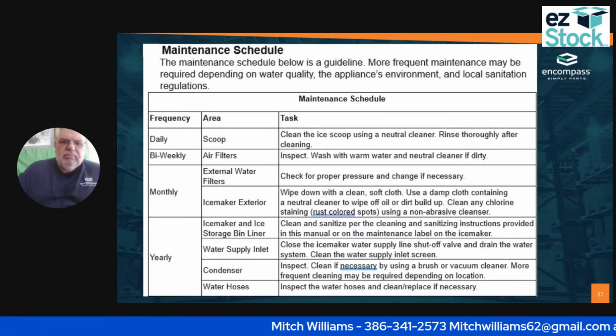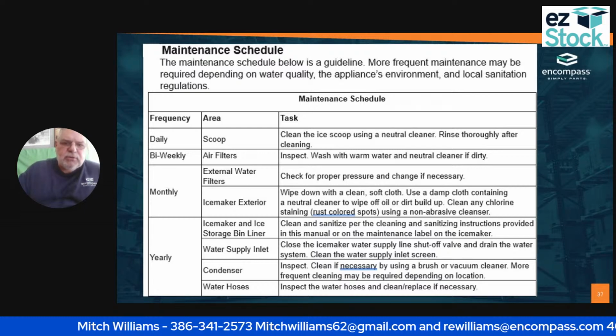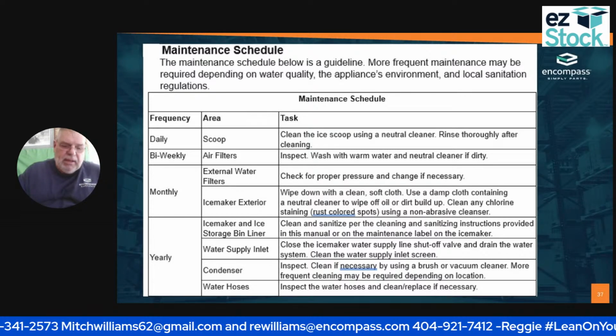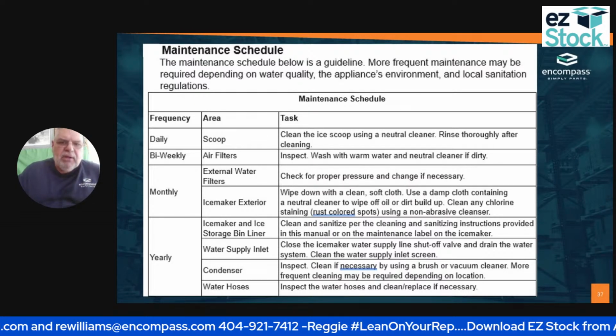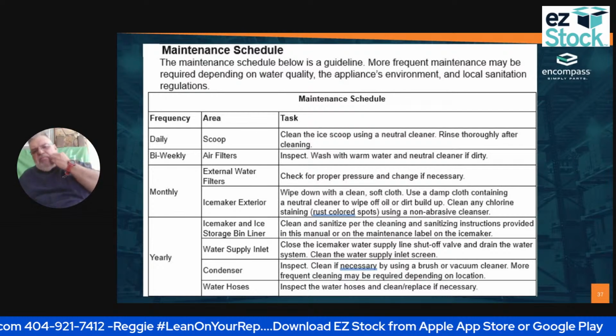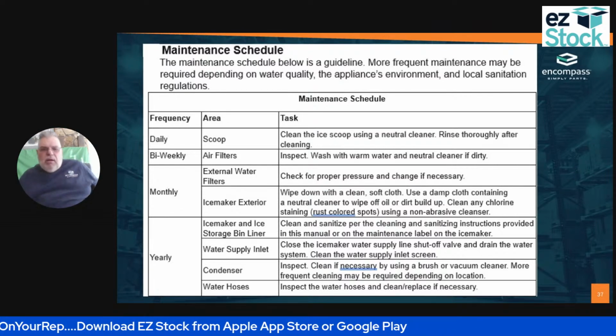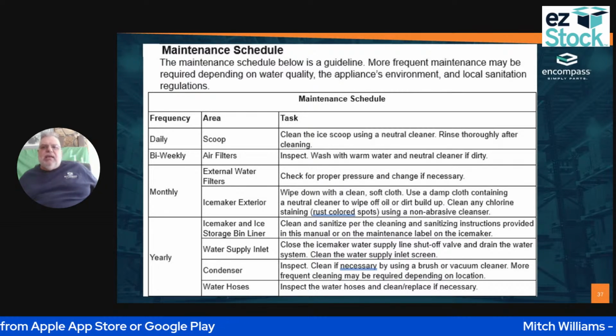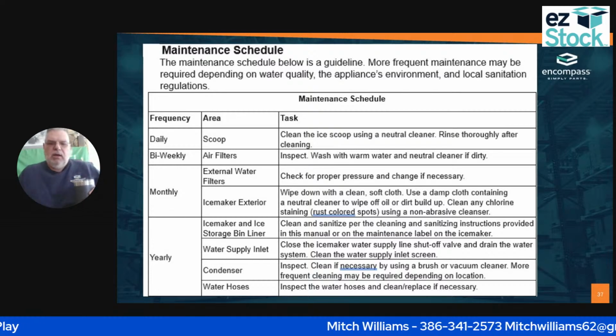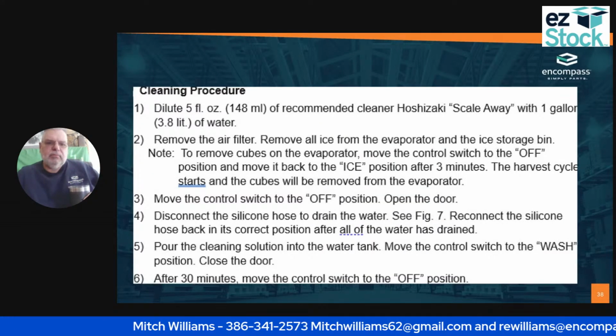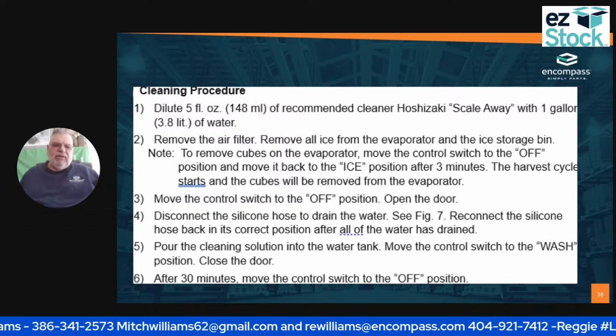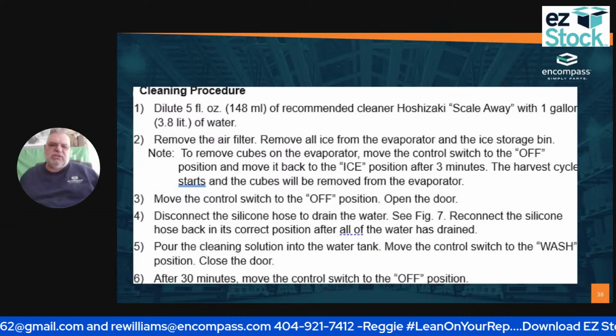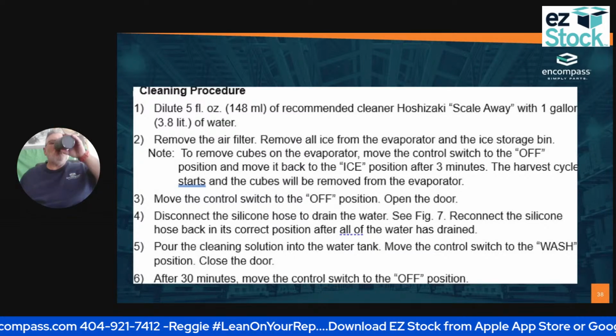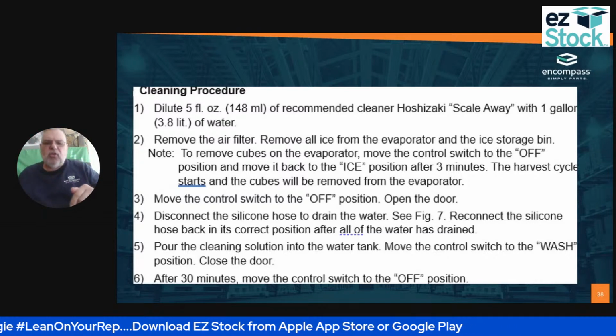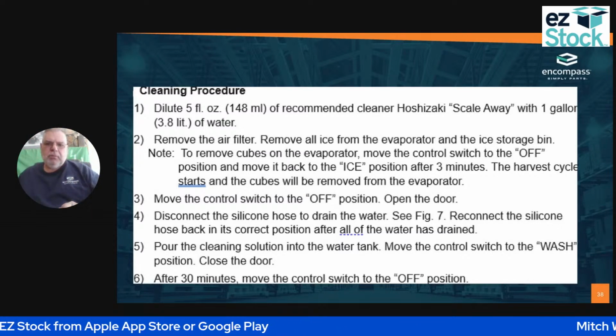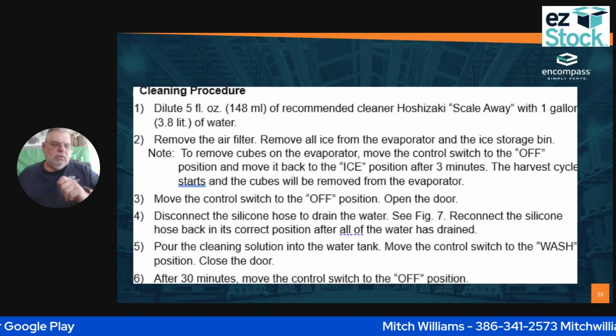Okay. Biweekly, once again, I'm going to check all of my air filters, which I can find whenever I drop my toe plate. Monthly, my external water filter. It may not be monthly, it may be bi-monthly, but at least once every couple of months, I need to be checking to make sure that my water filter is working properly. Then the cleaning procedure: I'm going to dilute 5 ounces of the recommended Hoshizaki Ice Scale Away with 1 gallon of water. Okay. So this one is a little bit more solution, which is called Scale Away, to the same amount of water.